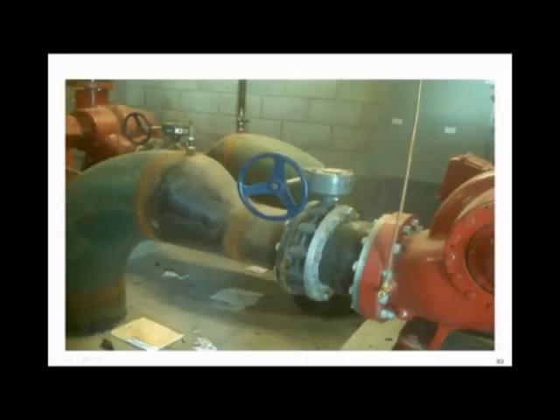I think this picture is worth a lot. I hope you recognize this picture. It's not your job, obviously. But eccentric where? On the bottom. Where should it be? On the top. They had air problems. They had air problems on the suction side of the pump. What did they do? They put gauge tappings on the tops of those little eccentric fittings to get the air out. But you know what? They had a slightly negative pressure and more air went in. They had a nightmare. This is the one I was telling you about that broke the shafts into. And it ain't our fault when you do things like this. You've got to help us out a little bit. But you've got to recognize it's not unusual to have slightly negative pressures on the suction side of a pump. And you're going to always have air. So those are the two things you've got to deal with. And we can't change the basic laws of physics. Hopefully your jobs never look that way.